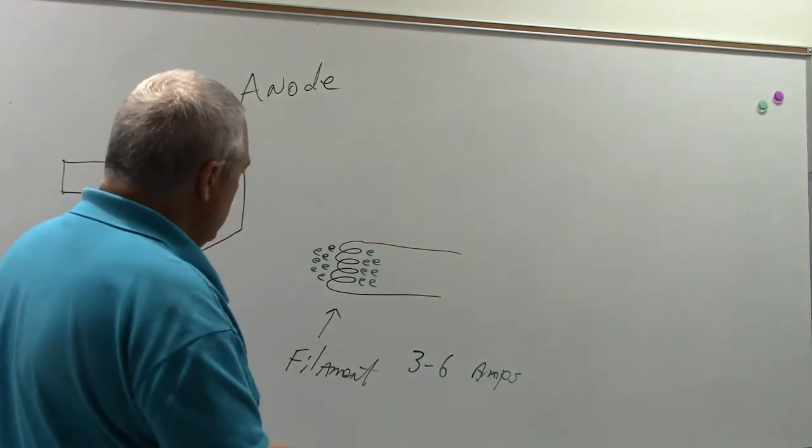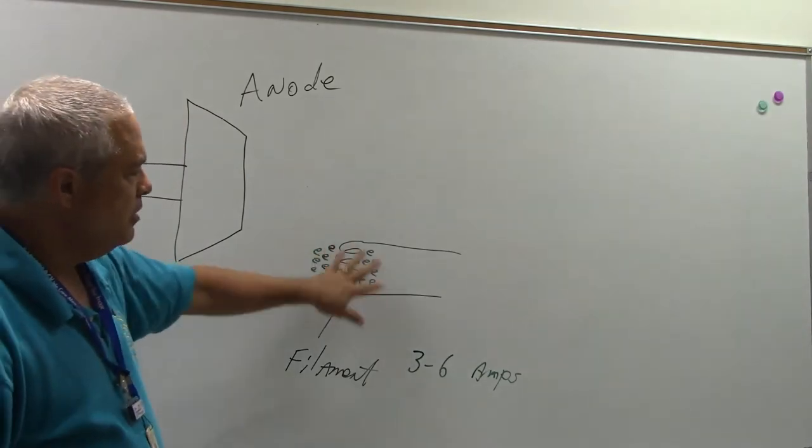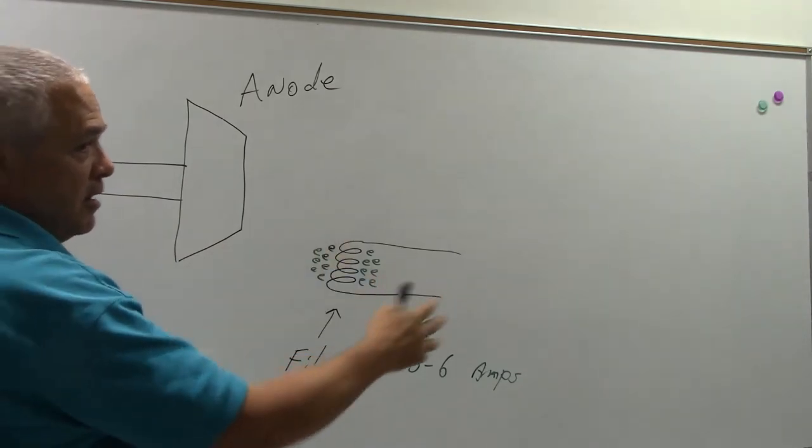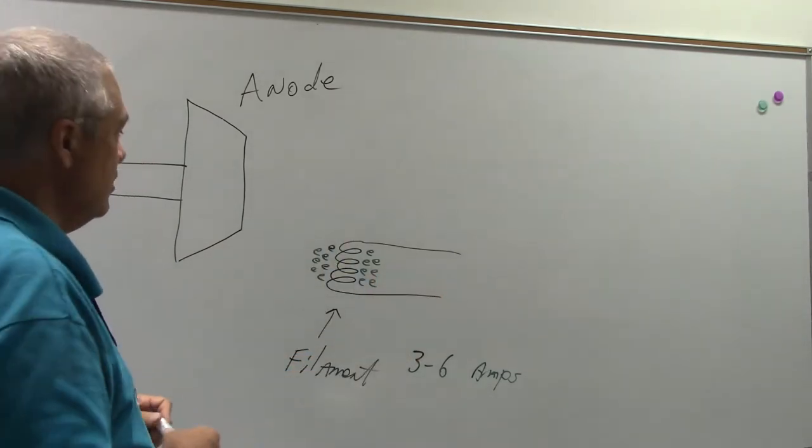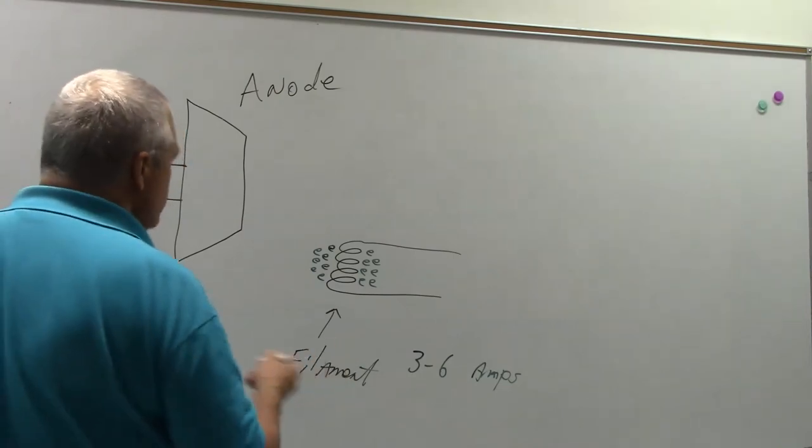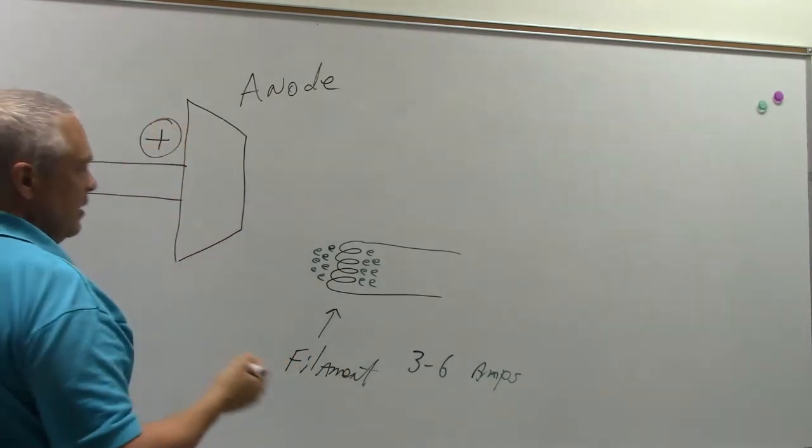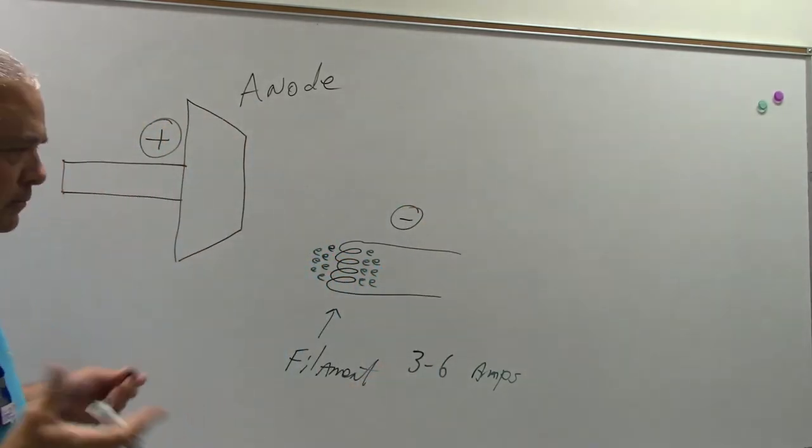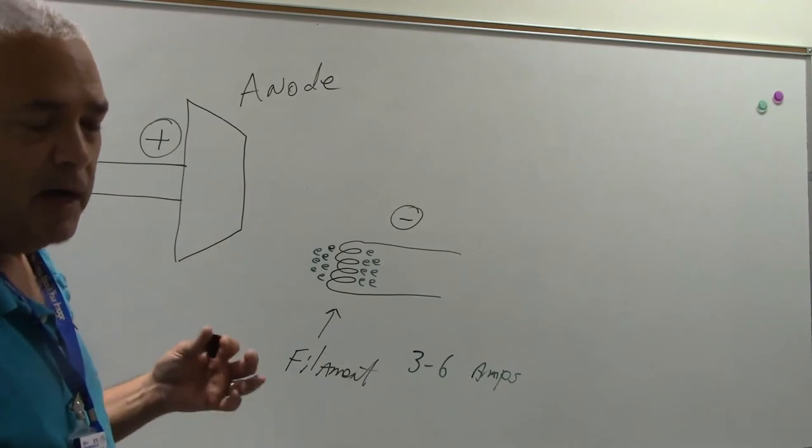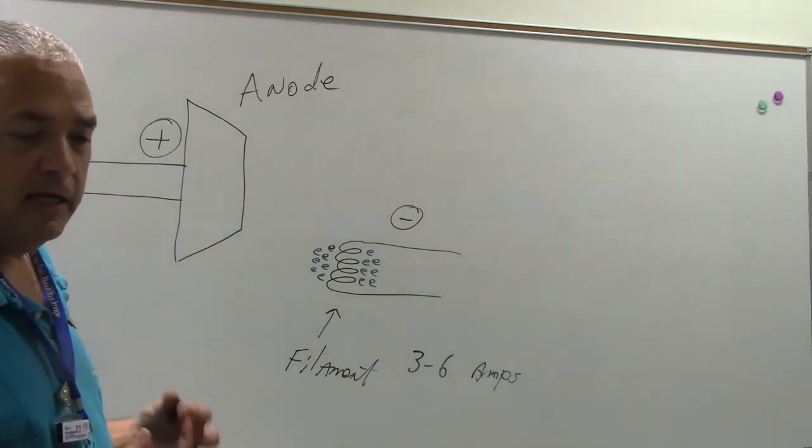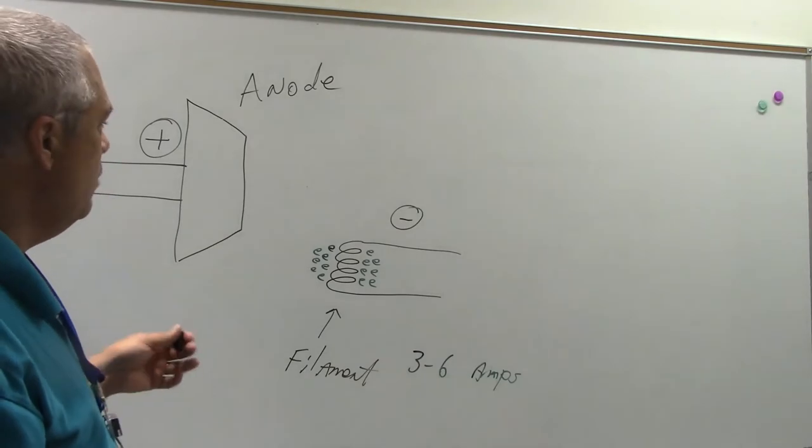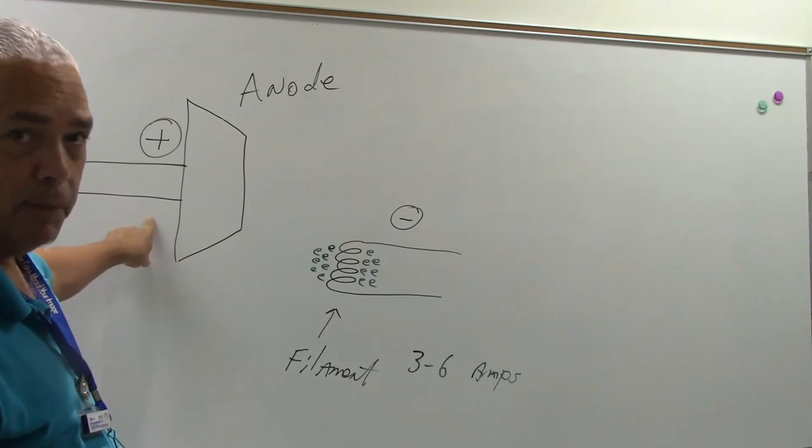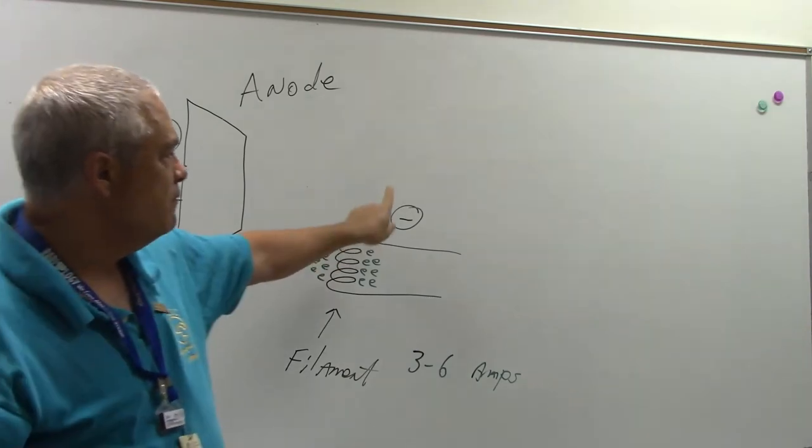So, what winds up happening, I've got a bunch of electrons here, and I've charged the entire circuit with DC current. So, I've got a positive charge on the anode, and I've got a strong negative charge on the cathode. And typically, if I've got my kilovoltage set for 80 kVp, then what's going to wind up happening is I'm going to have about 40,000 volts positive and another 40,000 volts negative.